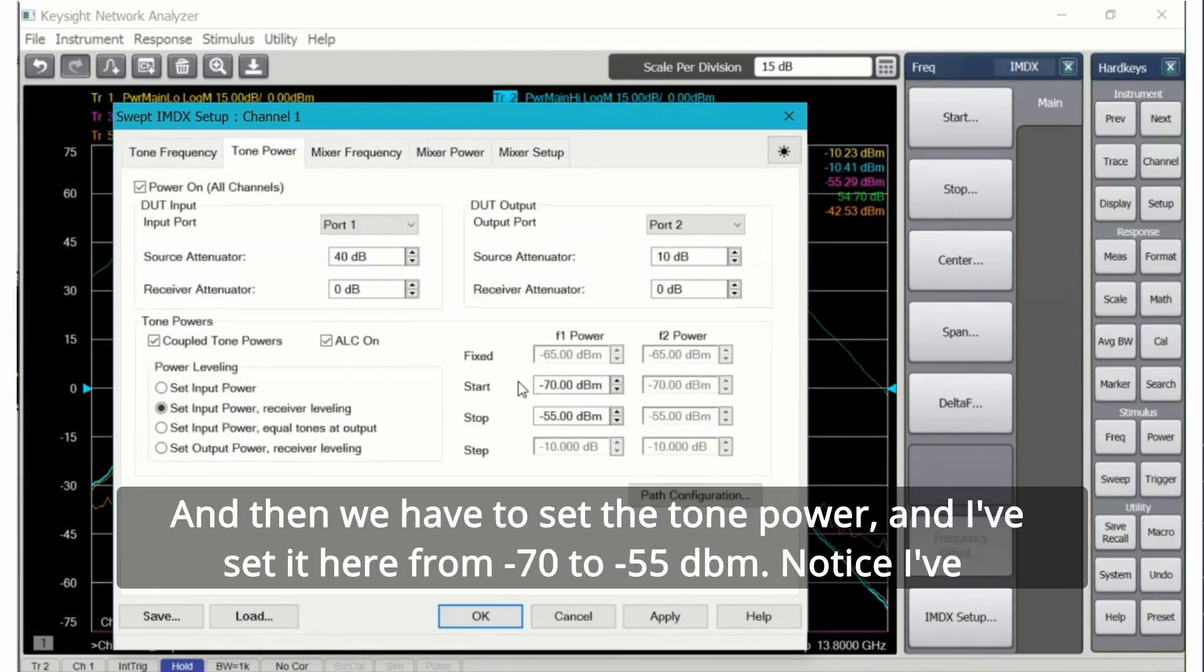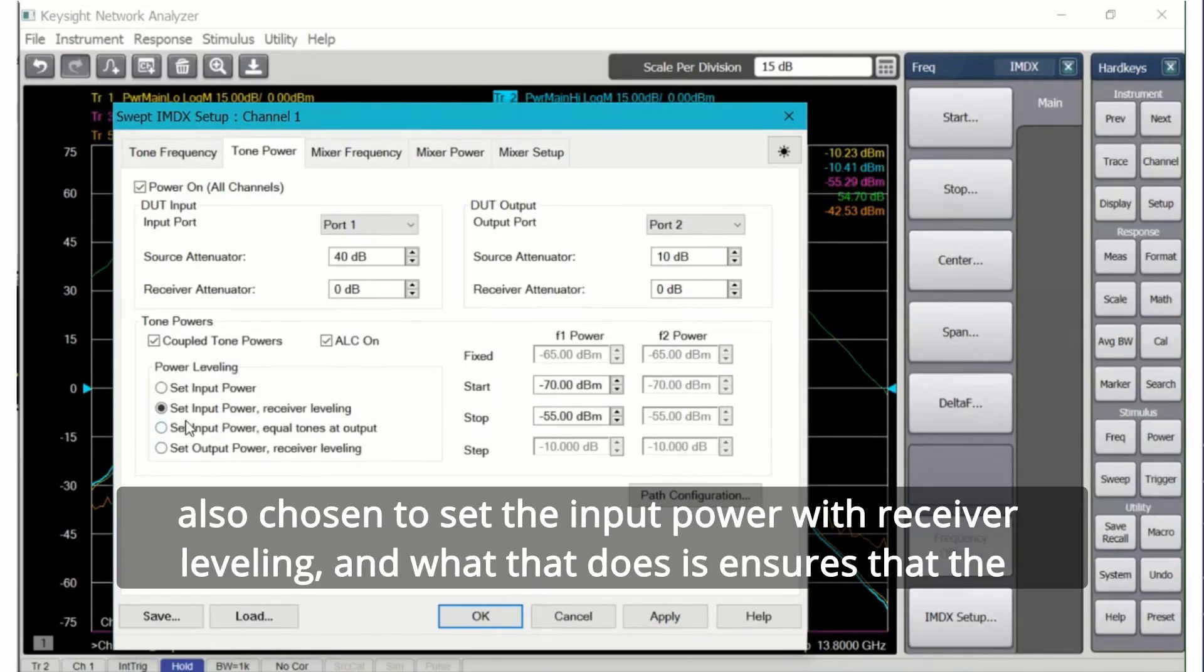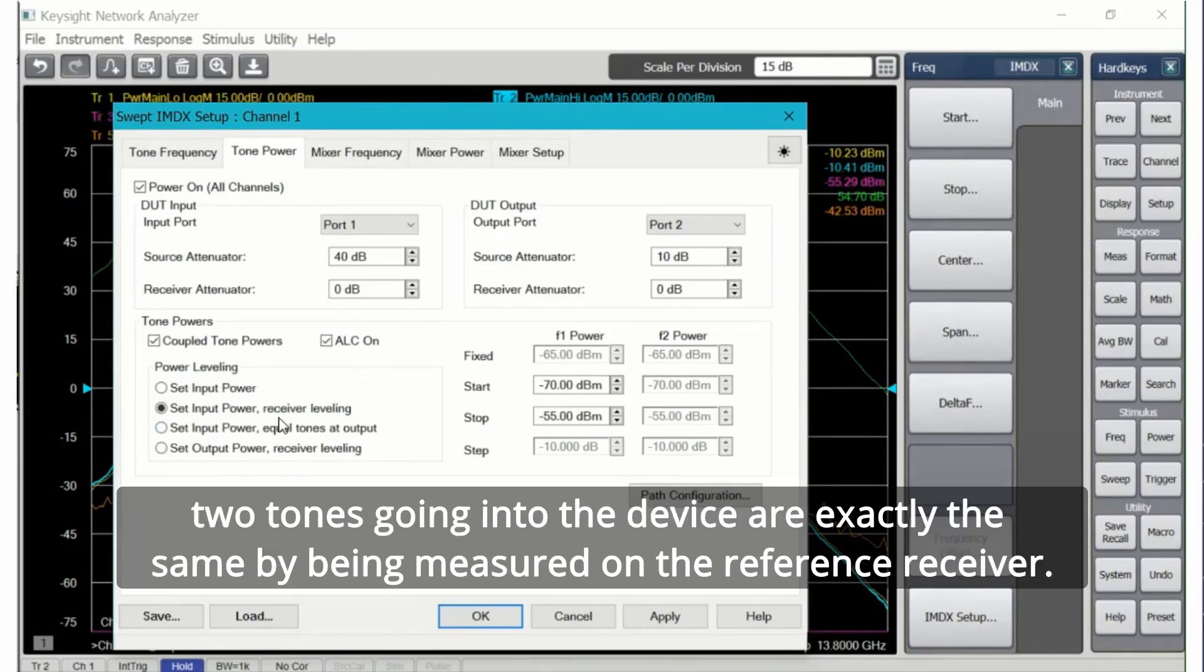Then we have to set the tone power and I've set it here from minus 70 to minus 55 dBm. Notice I've also chosen to set the input power with receiver leveling and what that does is ensures that the two tones going into the device are exactly the same by being measured on the reference receiver.